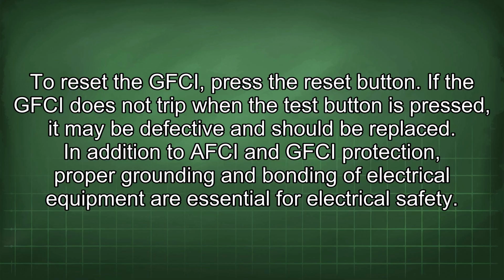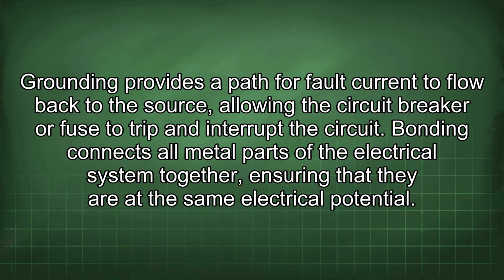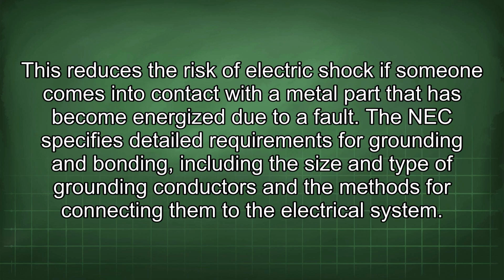In addition to AFCI and GFCI protection, proper grounding and bonding of electrical equipment are essential for electrical safety. Grounding provides a path for fault current to flow back to the source, allowing the circuit breaker or fuse to trip and interrupt the circuit. Bonding connects all metal parts of the electrical system together, ensuring that they are at the same electrical potential.